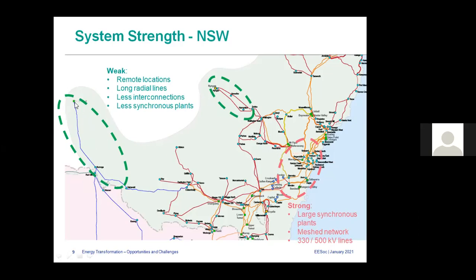Now you can see this line from Broken Hill to Buronga. It's about 250 kilometers long, a 220 kV line, one single line. But we have lots of wind and solar generation in this area. So what we can see is a fairly weak system from a system strength or fault level point of view, with less synchronous plant. You don't see a synchronous generator until you come to around Wagga, this Uranquinty power station. So all this is about 250 kilometers to Buronga, and then the line from Buronga to Darlington Point is about 400 kilometers. If you compare with Sri Lanka, it's almost wider than Sri Lanka and a similar length to Sri Lanka's.